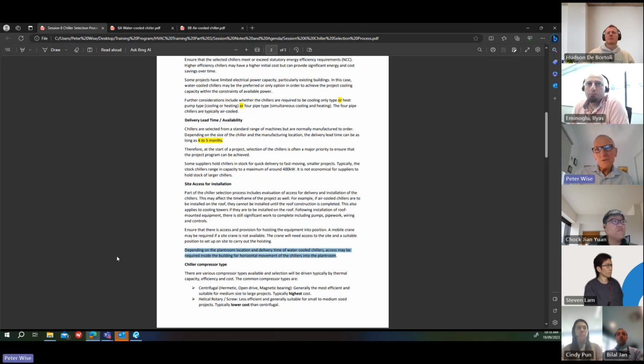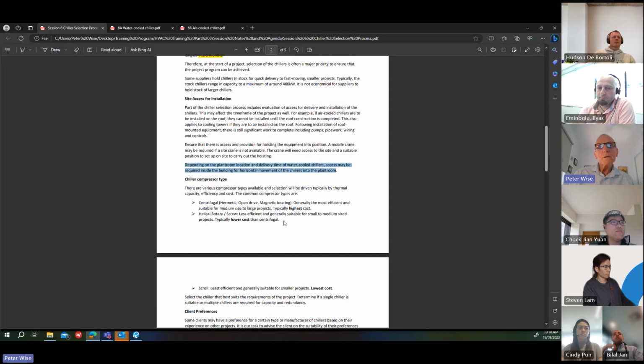A lot of these things are based on my experiences over the years. We did a hospital job once where we had a very large hospital, large horizontal floor plate, about 4,000 square metres on each floor. And the chillers were sort of in the central plant room. So we had to land the chillers on the outside of the building and then skate them through the building to the plant room. And that's quite a task, or it can be. So another thing to be aware of.